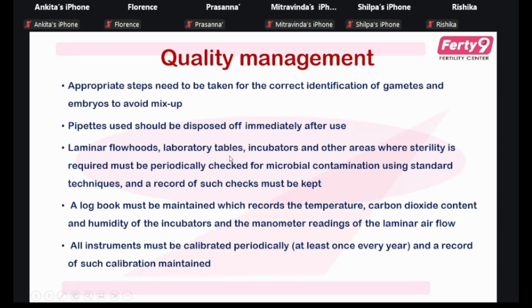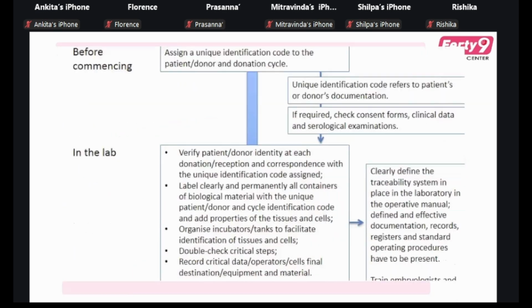Laminar flow hoods, laboratory tables, incubators, and other areas where sterility is required must be periodically checked for microbial contamination using standard techniques, like we take swabs twice weekly to identify any bacterial contamination. A logbook must be maintained which records the temperature, carbon dioxide, and humidity of the incubators, and the manometer reading of the laminar airflow. All instruments must be calibrated periodically, and a record of this is maintained inside the lab. So this is how we avoid the mismatch.